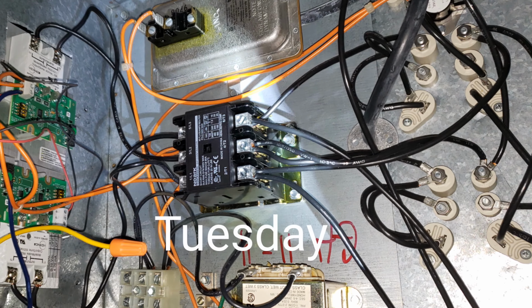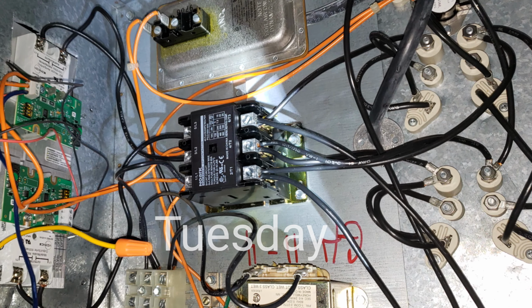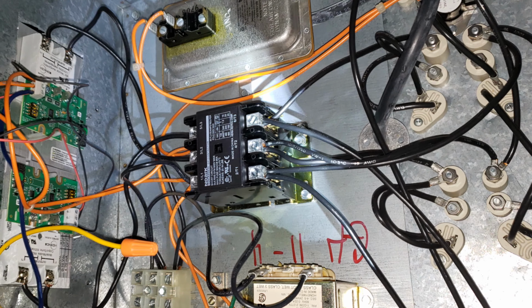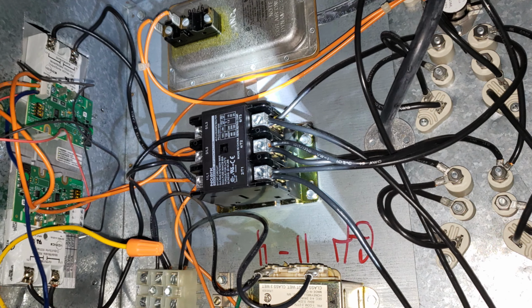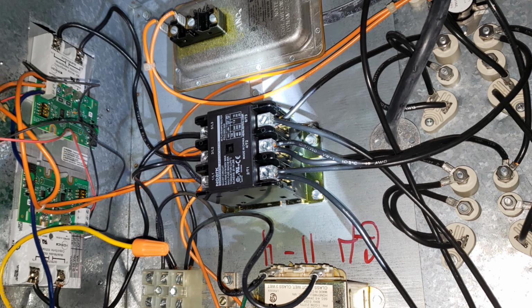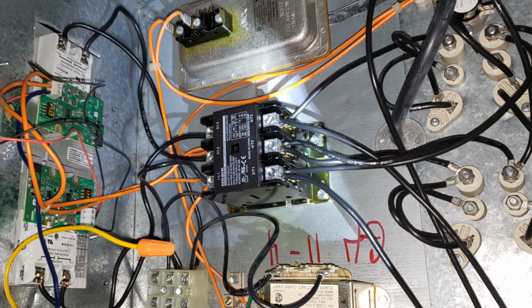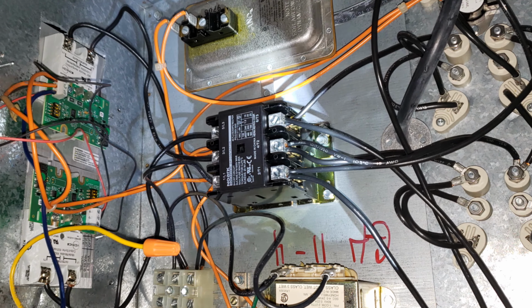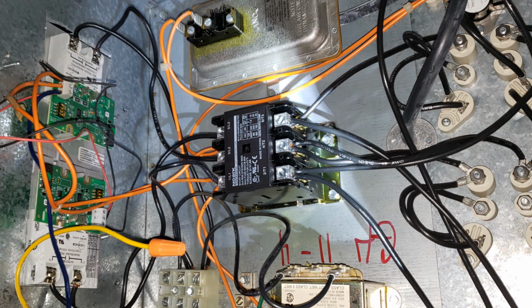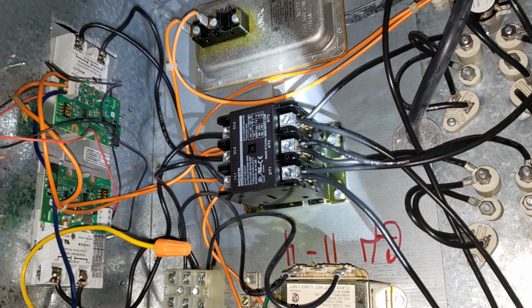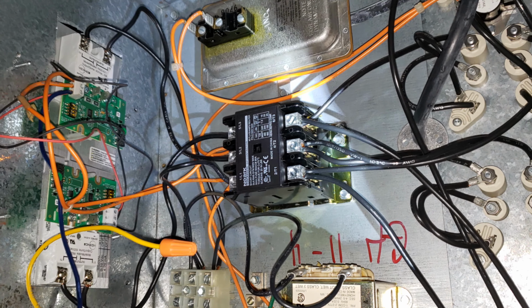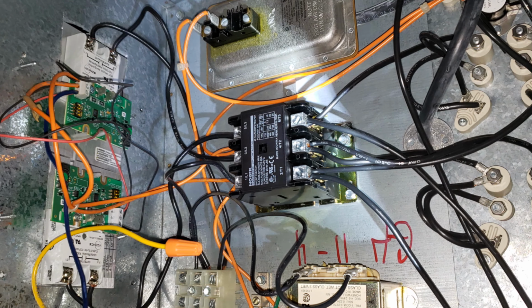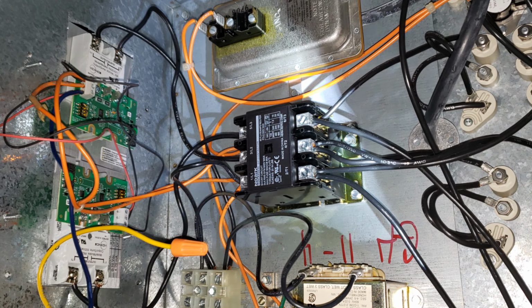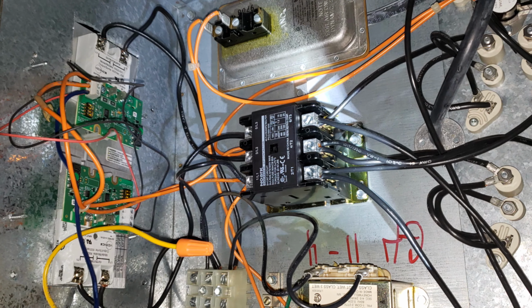So this is a heater cabinet. This is a heater that has SCR heat in it. You can see them there with the white squares. So what happened here is the original SCR heater went out, and it failed. It shorted to ground to itself, and it wasn't actually controlling the heat.